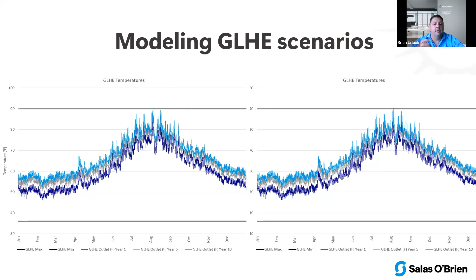We're modeling this, and as you can see here, this is very cooling dominant. We never get below 45 degrees, but you can't reduce your bore field anymore because we're hitting that 90-degree mark. So now if we could take care of those couple of hours on that peak, we could probably shave another 10 bores out of the system, and just handle that peak differently. So those are some of the things that this really helps show you - very detailed, how I can manage my system and try to reduce costs.